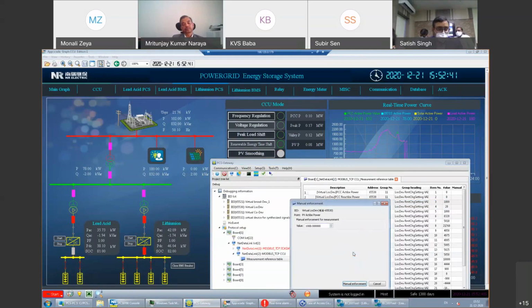And let us see what is the live generation as of now. So as of now, this is generating 100 kilowatt as of now, isn't it? So for example, it is generating 100 kilowatt now, but we need say 80 kilowatt from this combined facility. So here I'll also make it clear that once we say PV smoothing and PV applications, it has to be co-located, and the charging or discharging should merge with the power output from the PV. But however, we didn't have that facility at that time when we conceived the pilot. We assume that any kind of discharge from the battery is getting absorbed or discharged by the solar rooftop. So that was the basic assumption which we made for the testing purpose.